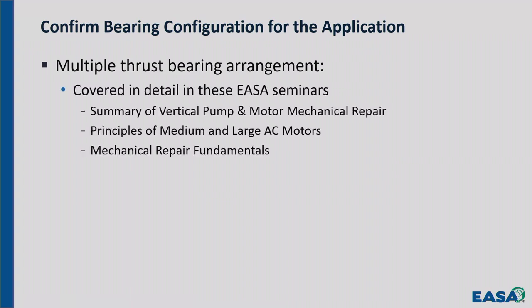if you want to know more about it, we have a one-day seminar we do on vertical pump and motor applications where we cover it extensively. Principles of medium and large AC motors covers it, and mechanical repair fundamentals covers it. Those are three EASA resources available for more information on bearing configurations. Okay? We mention it here because where does the problem come up? It's installed, the bearing's running hot, the bearing is noisy, or there's some other related problem, or the bearing failed.